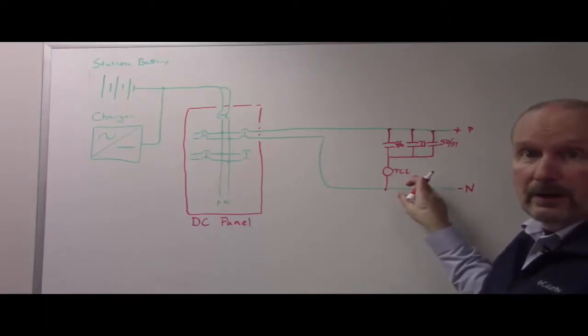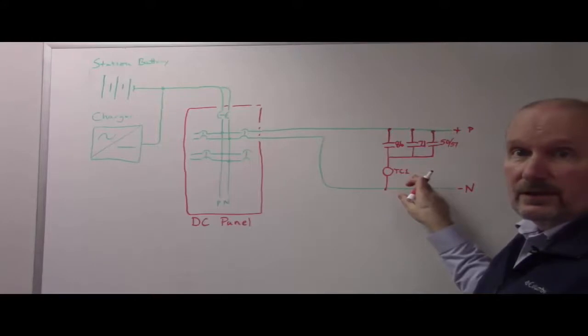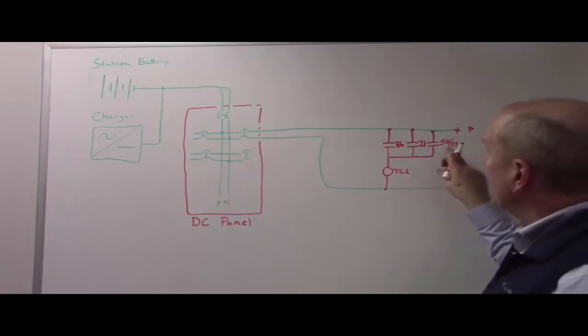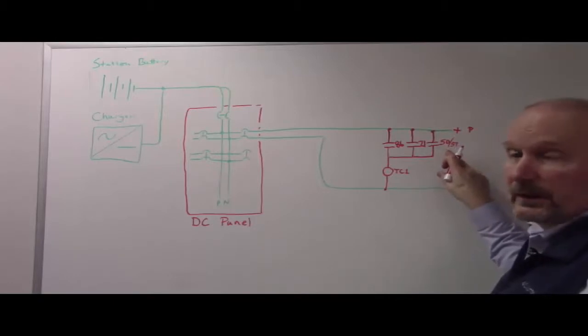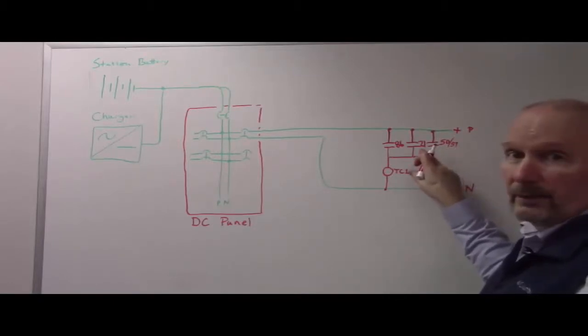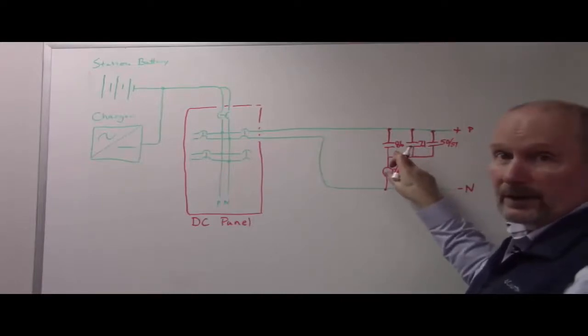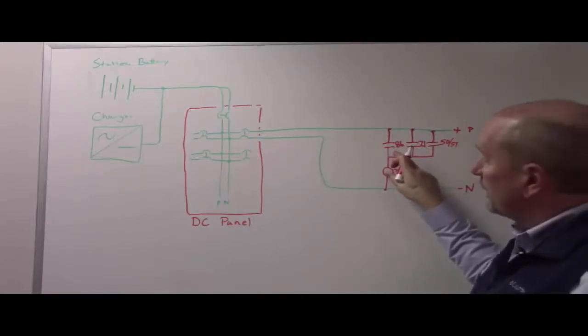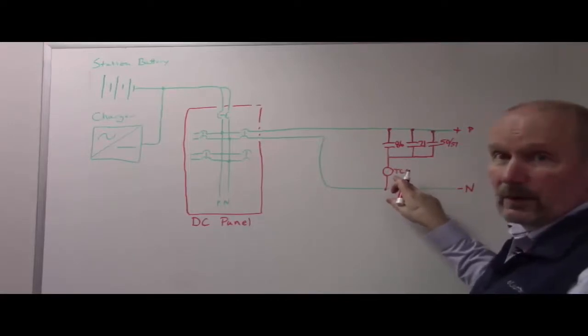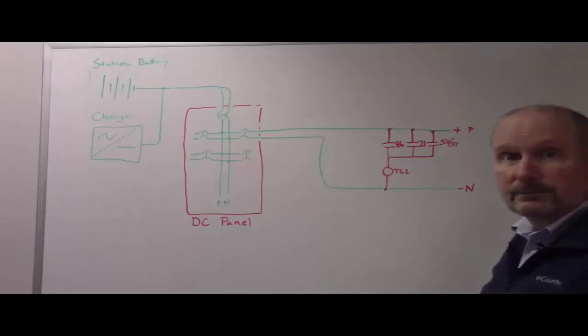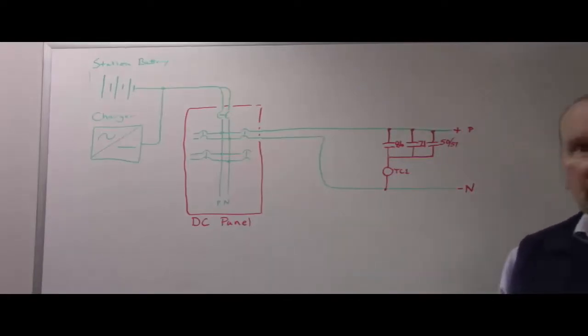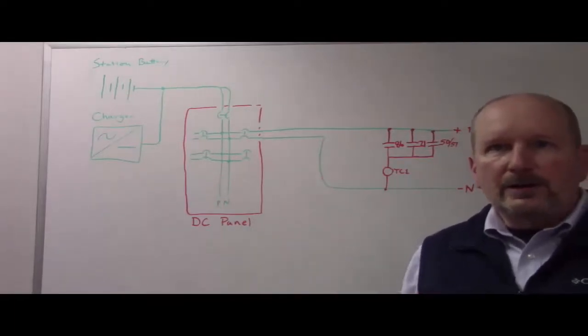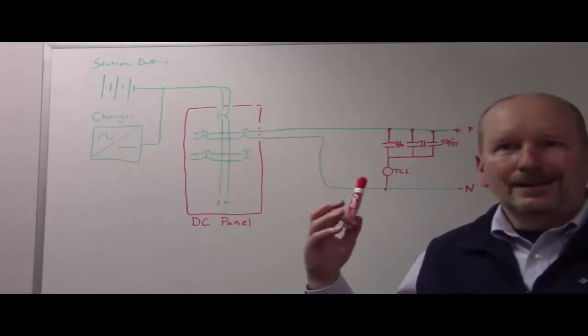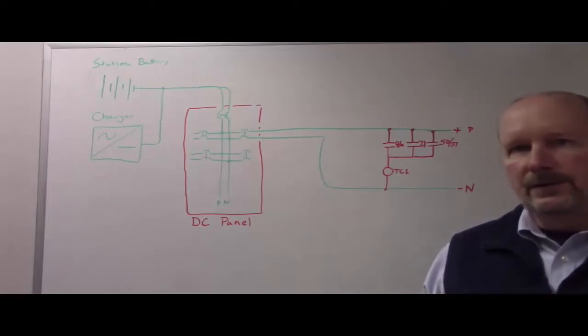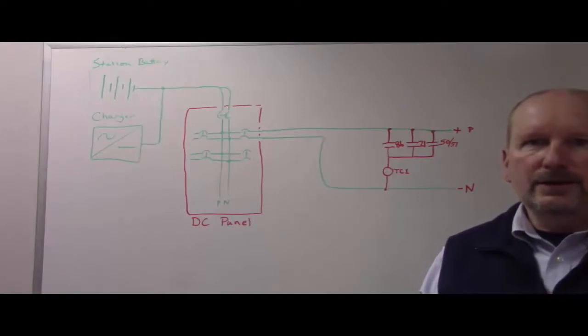Now presumably the breaker is already closed, and whatever we're energizing is in service. However, if you have an overcurrent, which is a 50/51, or an impedance relay picks up, or a lockout relay picks up, notice it's all OR logic, then you're going to energize that trip coil and the circuit breaker is going to trip. It's very simple, nothing really fancy about this, and every circuit breaker has one of these. This is really fundamental, simple logic that you really want to have an absolute intuitive level understanding of.